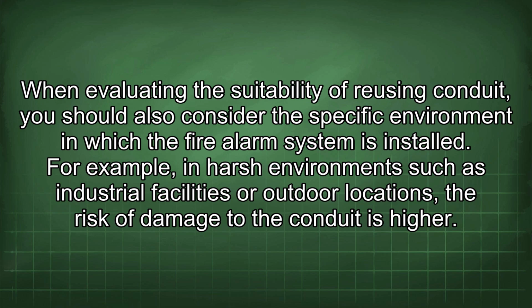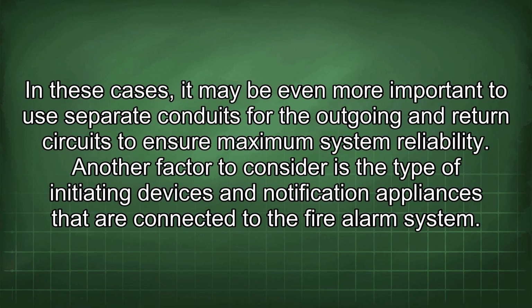For example, in harsh environments such as industrial facilities or outdoor locations, the risk of damage to the conduit is higher. In these cases, it may be even more important to use separate conduits for the outgoing and return circuits to ensure maximum system reliability.